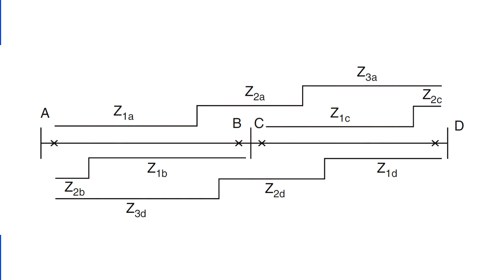Zone 1, or Z1A, is the first line of defense. Covering roughly 80% of section AB, Z1A is critical for quick action. Known as the high-speed zone, it operates without any intentional delays. When a fault occurs within this zone, the response is immediate, with no intentional delay.